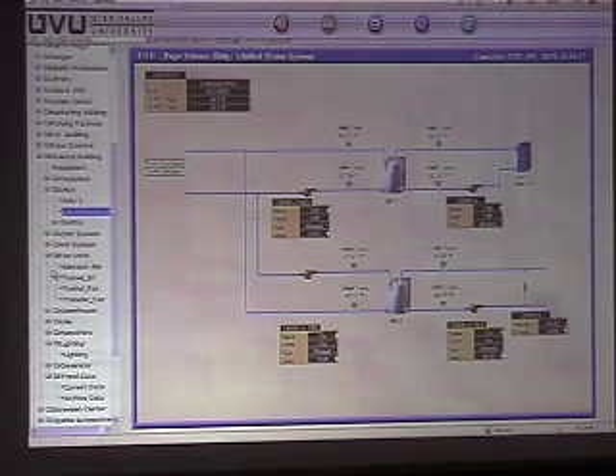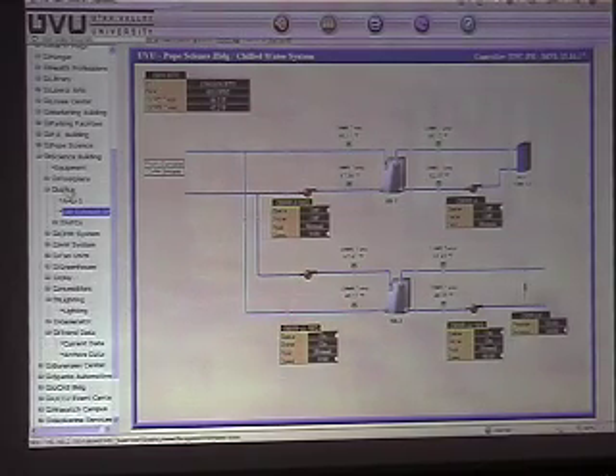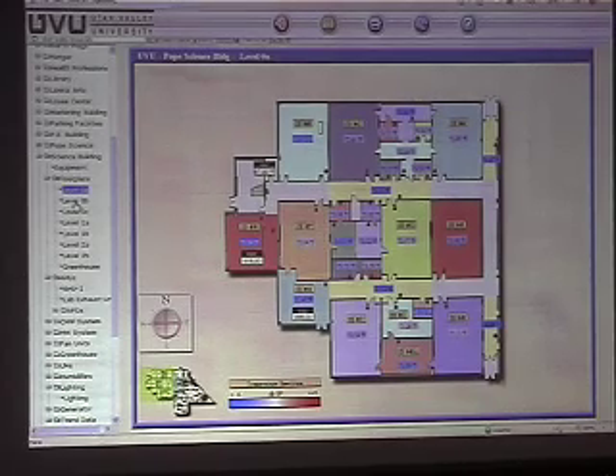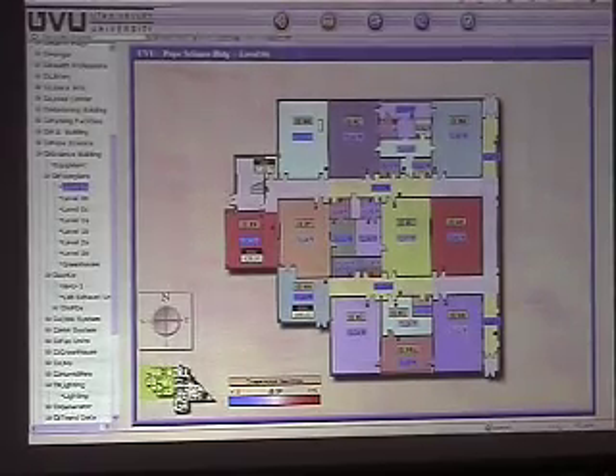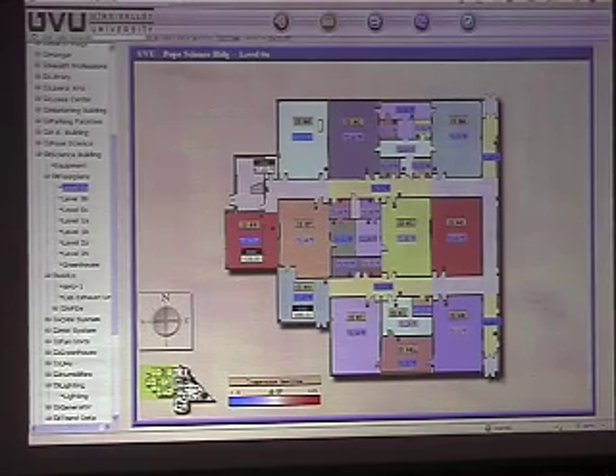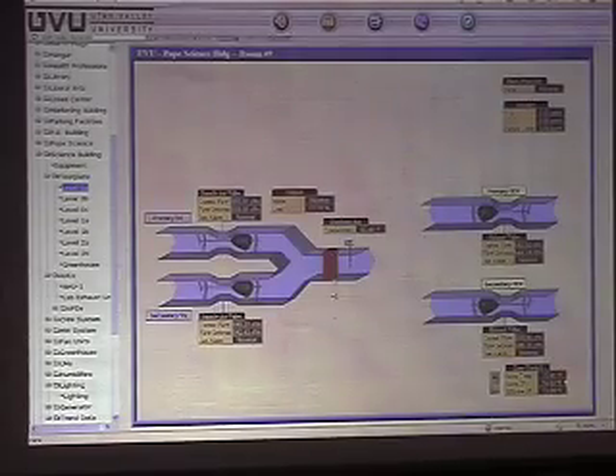Let's see. There are some fan coil units. Let me go over the floor plans here. So we've got your floor plans for each level. We broke them up into sections just so that you can see the rooms better, make them bigger. We show down here on your key what section of the entire floor this floor plan incorporates. So we've got some rooms where we're directly monitoring CO2. Your VAV, your room temperatures are shown here. And just like the other buildings, you've got your backgrounds that represent your temperature set point differential there, and your links with the thermostat that'll take you to your piece of equipment.